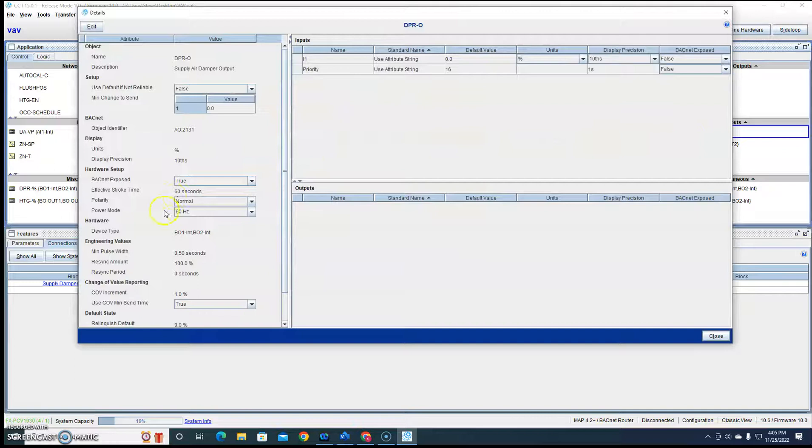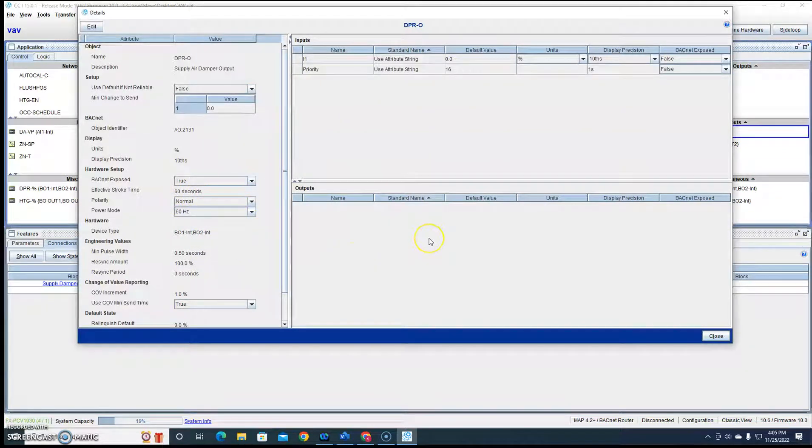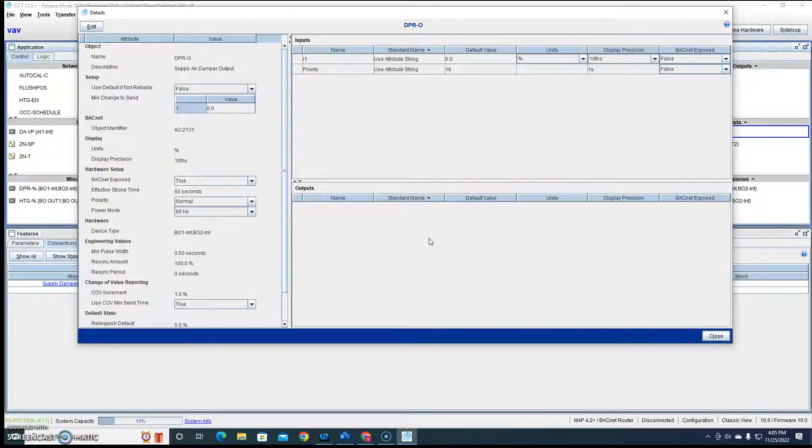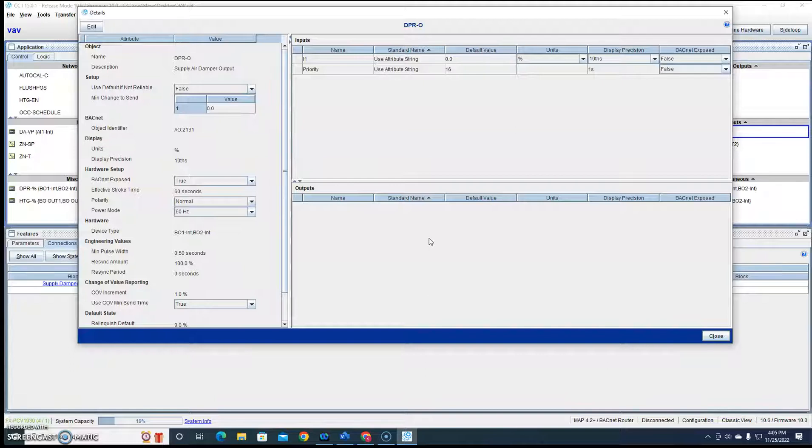And it's set up for 60 seconds. So what's that going to do after 60 seconds, it's going to turn off the power going to the direction. So if it goes fully open from a fully closed position, you've got 60 seconds of power going one way, and then it's going to stop until it needs to go the other way.